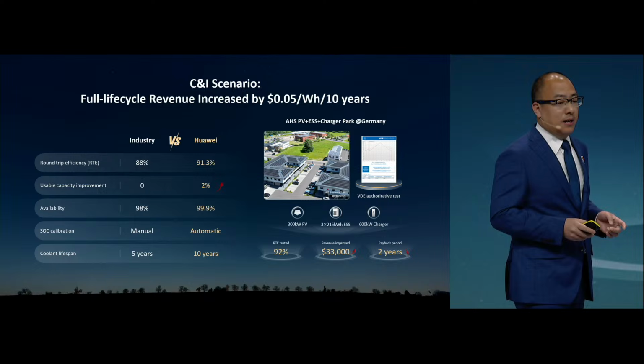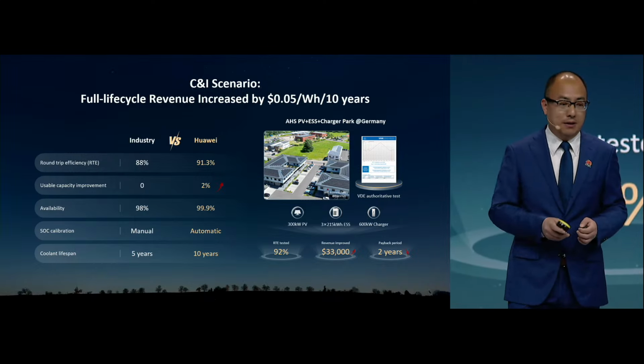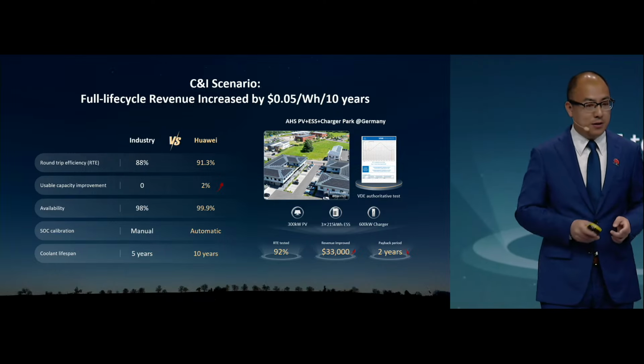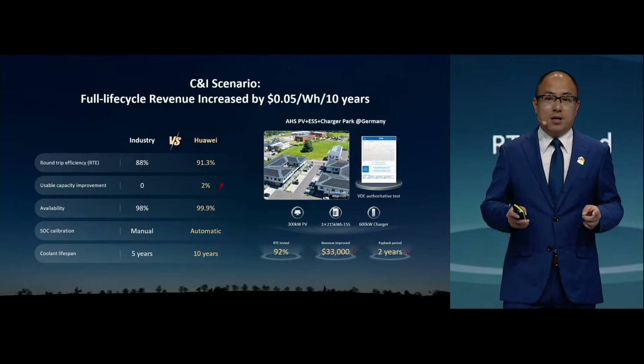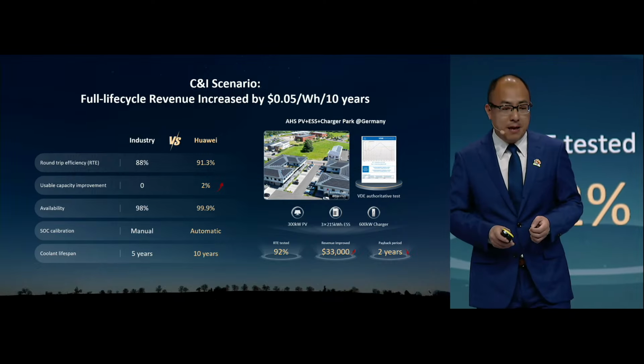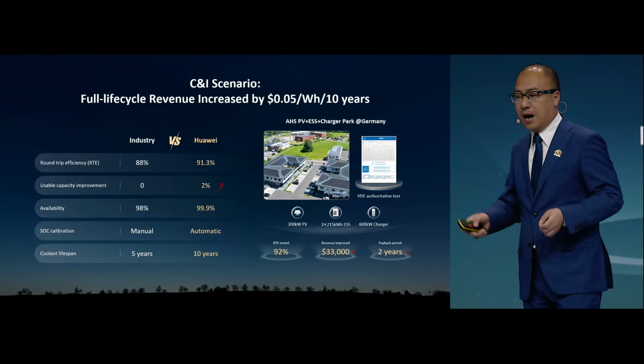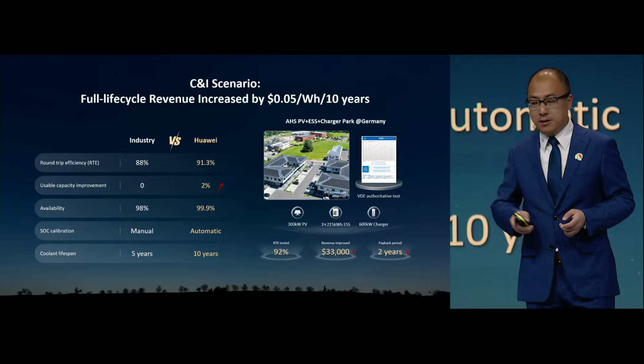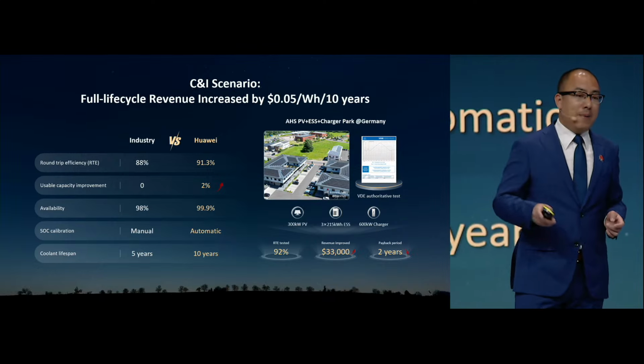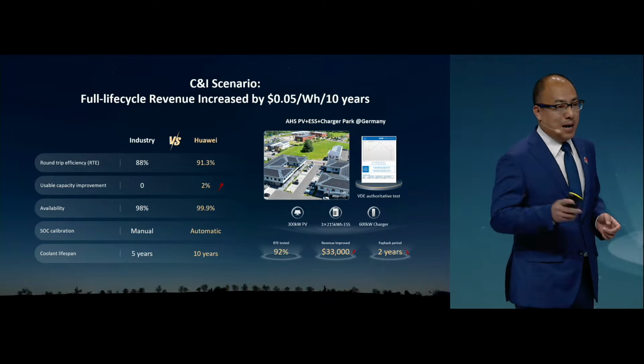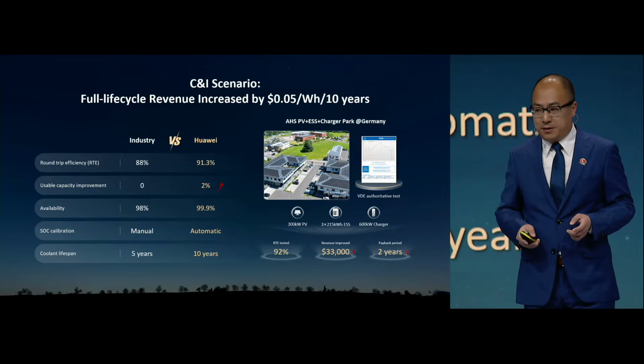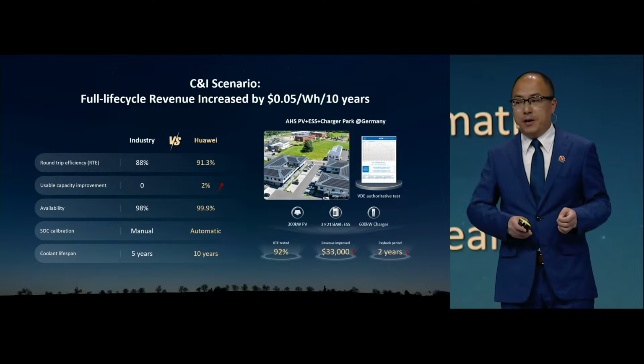In the C&I scenario, take the AHS Business Park project as an example. Thanks to the high round trip efficiency, up to 91.3%, which is 3.3% higher than that in the industry, and the usable capacity is 2% higher. It is estimated that the revenue will be increased by 33,000 euro in 10 years compared with traditional BESS. And the payback time of the project is shortened by 2 years, from 7 years to 5 years. VDE performed professional tests on the plant, showing the RTE reached 92%, even higher than Huawei claimed.